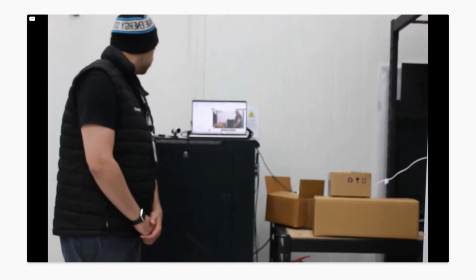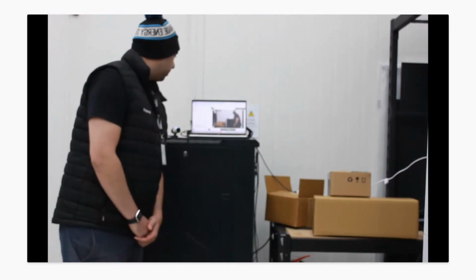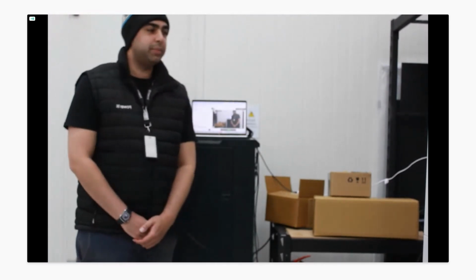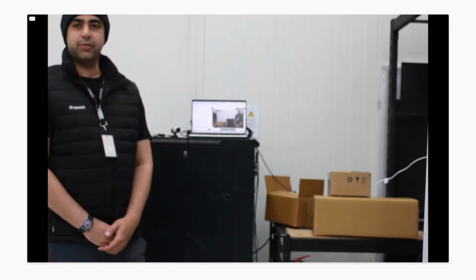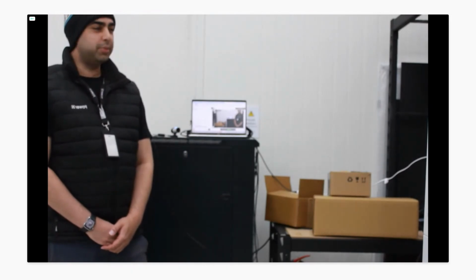And there was a question about off-grid there from Jason, I think. So we do have the ability to control a generator, turn it on and off for off-grid. Suitable for off-grid - PowerPlus have done a lot of off-grid, and we use big inverters with transformers inside them. So this system here, transformerless, for 7 kilowatts, it is the peak for off-grid. So you won't have that extra surge that the off-grid design inverters will give you.